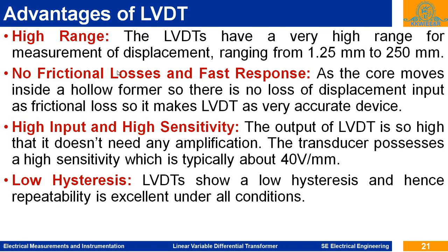Because of that, the response of this LVDT is very fast. There is no friction, no loss, so response is very fast. No loss of displacement input as frictional loss, so it makes the LVDT a very accurate device. Next, high output and high sensitivity. The output of an LVDT is so high that it doesn't need any amplification. Depending on your input voltage, your output voltage is decided.